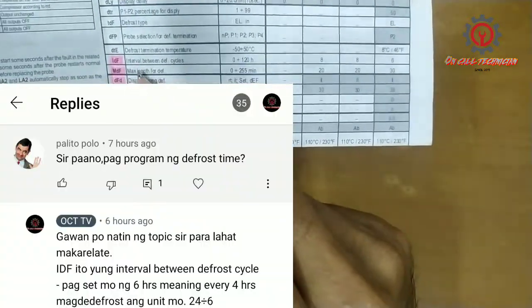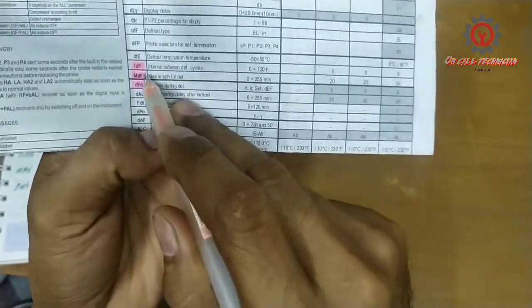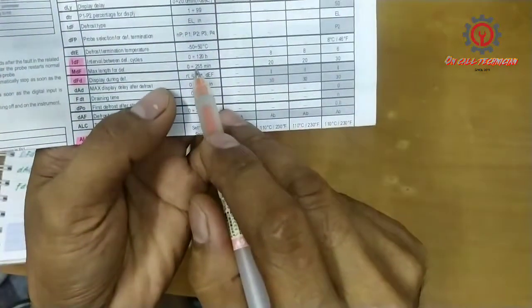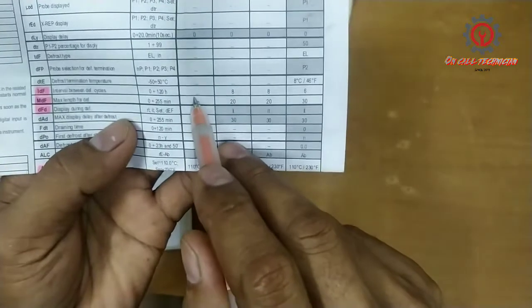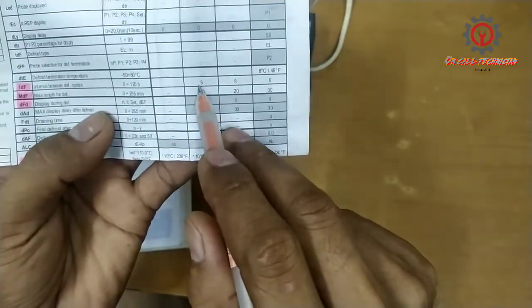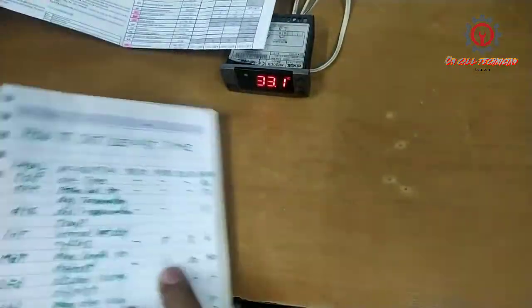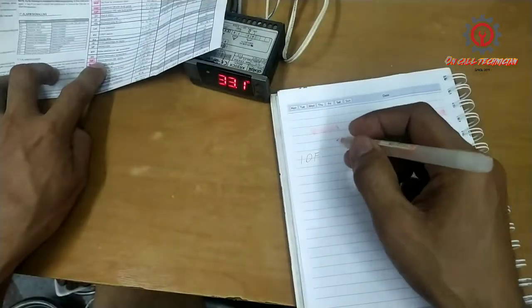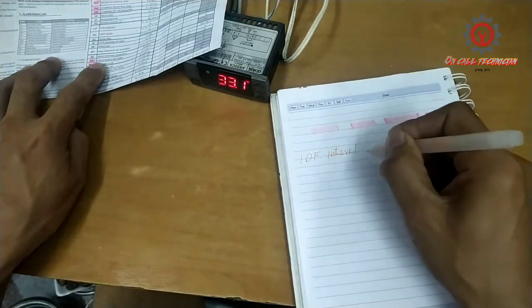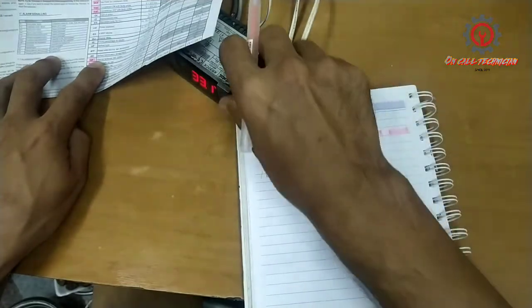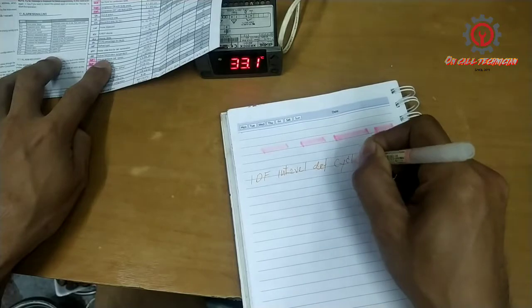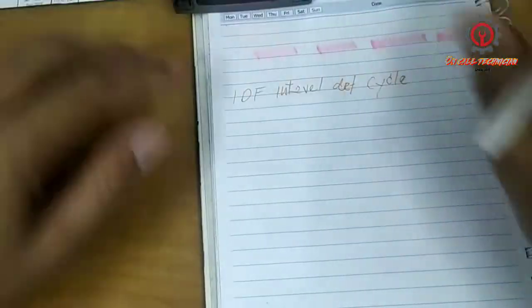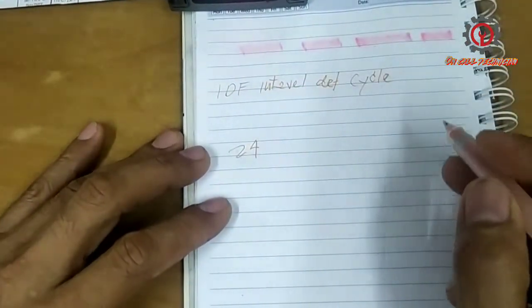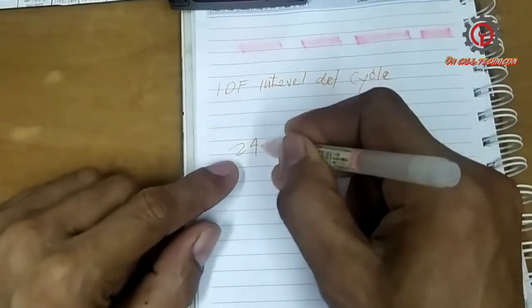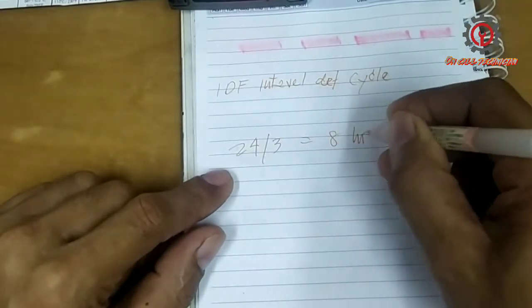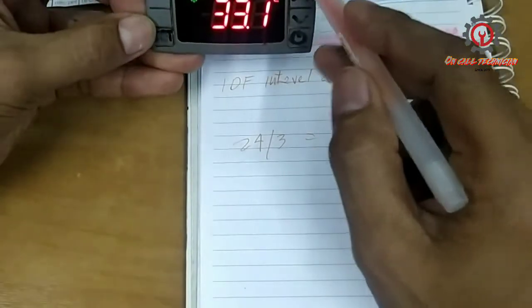And this is the question: how to set the defrost time? And here guys, the IDF, I'm going to elaborate this one. It has a range of 0 to 120 hours. For the XR10 it doesn't have, but for the 20, 30 and 40 it has. And I'm going to elaborate that one. So here, under the IDF, this is an interval defrost cycle, and we have 24 hours a day. For example, I set that to 3 hours. 24 divided by 3 is equal to 8 hours, meaning every 8 hours a defrost will engage in this unit.